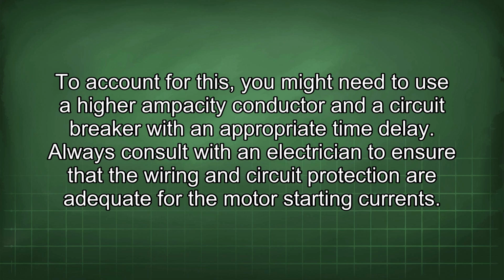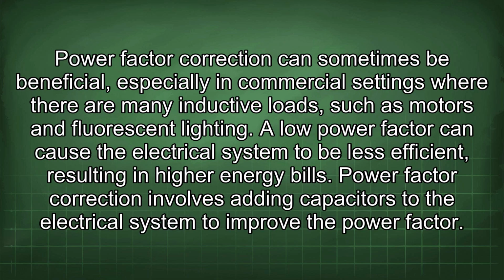Power factor correction can sometimes be beneficial, especially in commercial settings where there are many inductive loads, such as motors and fluorescent lighting. A low power factor can cause the electrical system to be less efficient, resulting in higher energy bills. Power factor correction involves adding capacitors to the electrical system to improve the power factor.